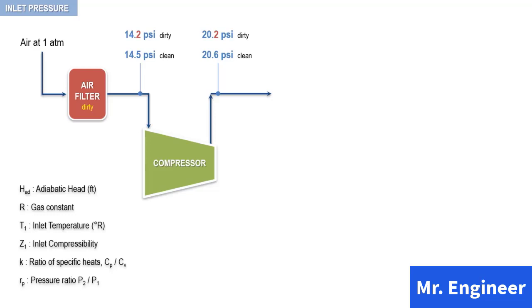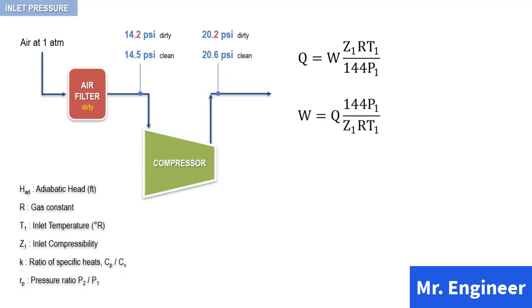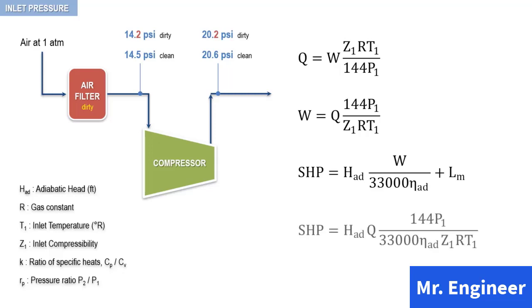As you can see, for a centrifugal compressor, a decrease in the inlet pressure will result in a decrease in the discharge pressure. Now, to assess the effects of a variation in inlet pressure, let's refer back to the volume flow equation. Rearranging it will give a new equation. Comparing this with the shaft horsepower equation seen in a previous video, we find that shaft horsepower is proportional to weight flow or inlet pressure.